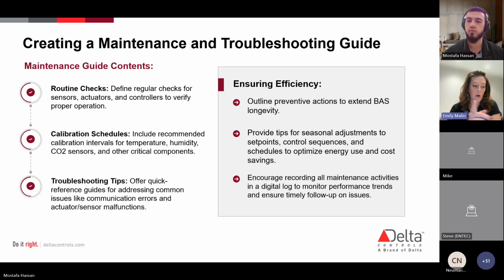What he's saying too is you want a hybrid, including a comprehensive guide for your BAS system. That will include more along the lines of your system architecture, your network diagrams, your communication protocol, maintenance schedules, and what some of those alarms might mean. Then the field manuals are for the device-specific procedures, and those come from the manufacturer, like Moose was saying when he ran through that diagram that had the chillers onboard. Those packaged units will have device-specific procedures, and oftentimes quick references for code errors on the prepackaged equipment. I think it would be helpful to have both. Got it. Thank you.